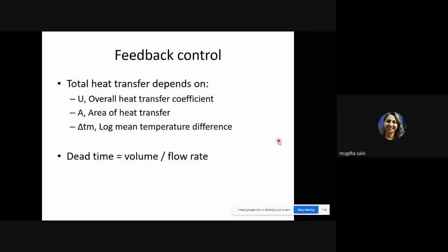Also, the dead time of the heat exchanger will be volume upon flow rate, because the point at which the fluids will enter into the heat exchanger and the point and the time at which they will exit, there will be a delay between the two, and the delay will depend on the volume, how much time the heat exchanger is taking to pass.